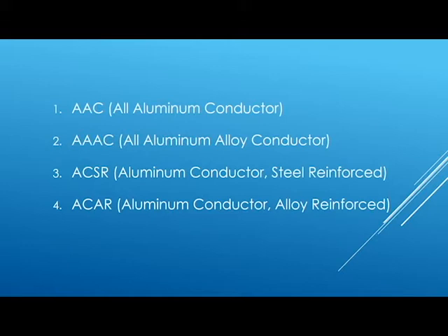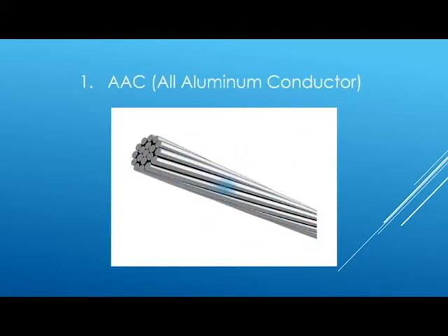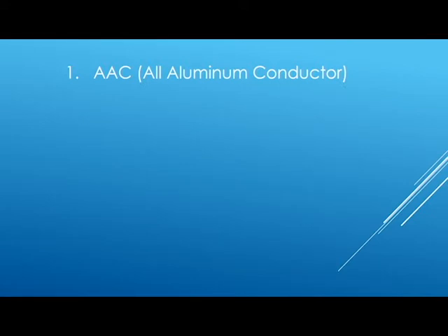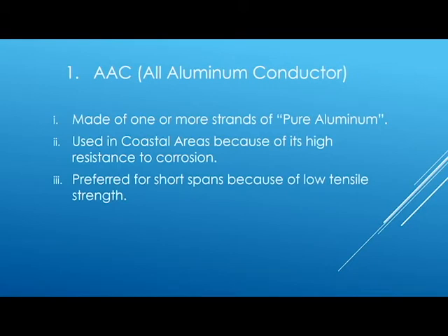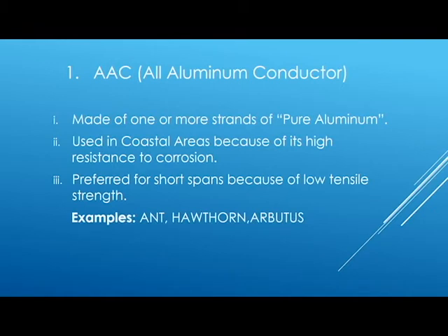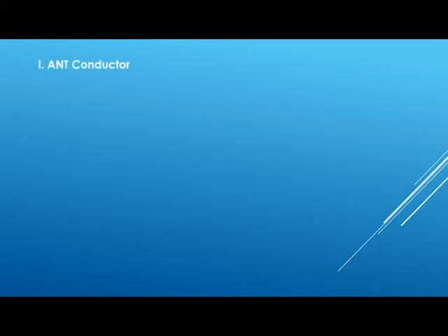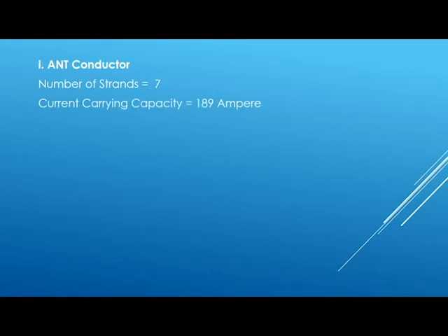First, we will discuss All Aluminum Conductor. All Aluminum Conductor is made of one or more strands of pure aluminum. It is mostly used in coastal areas because of its high resistance to corrosion. It is normally preferred for short spans because it has low tensile strength. Some examples of AAC conductors are Ant, Hawthorn, and Arbutus. The Ant conductor has a total number of seven strands.